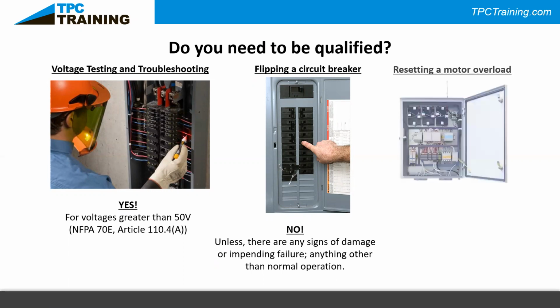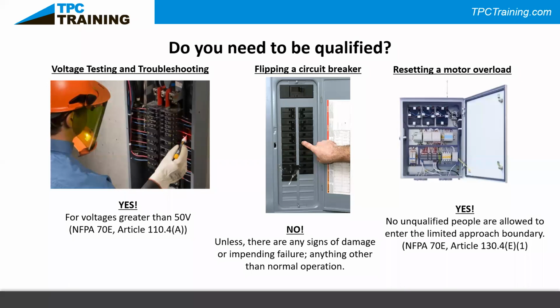Let's talk about resetting a motor overload. You walk into your control cabinet to press that little button to reset the overload. Not too bad, right? You just open the door, press a little plastic button, and close it. You don't need to be qualified for that, do you? Actually, yes, you do—because as soon as you open that door, you're exposing yourself to 480 volts of phase-to-phase voltage potential.